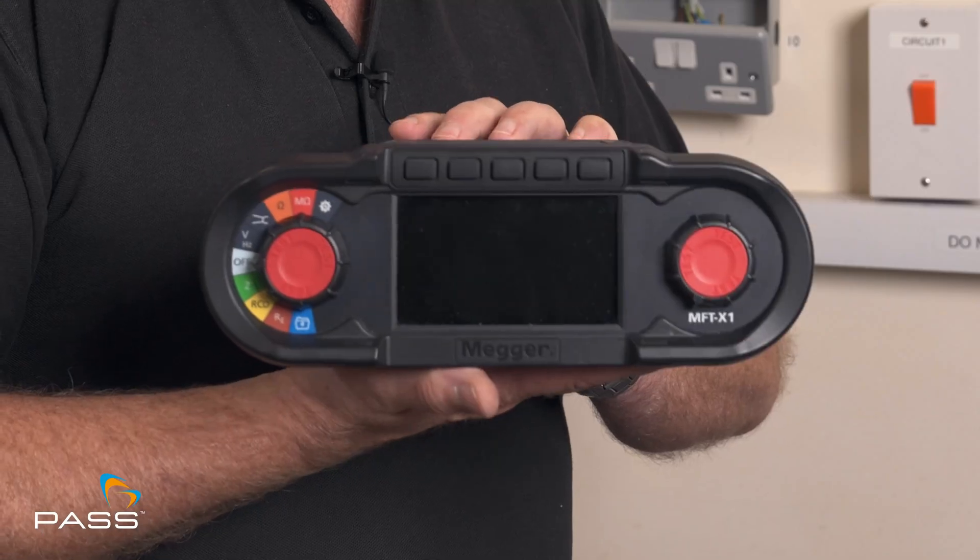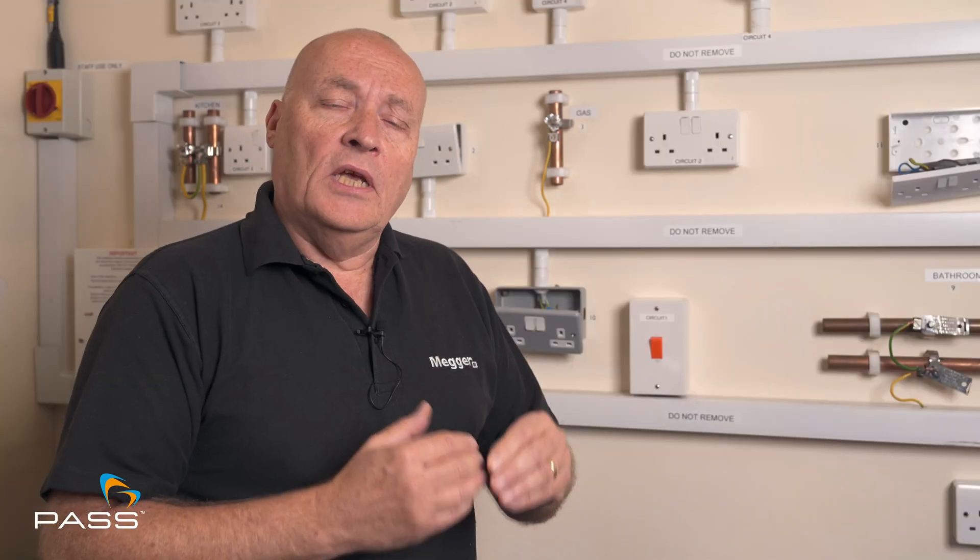Hi, I'm Peter Wade. I'm UK Sales Manager for Megger Limited and today I'm here with PASS in one of their test bays to show you how you can test an RCD or RCBO using our X1 multifunction tester. Carrying out an RCD test — what does that mean? Well, basically what you're trying to do is find out how quickly an RCD will trip and protect the circuit under a fault condition. There are set limits for this in the BS7671 and we need to abide by it.